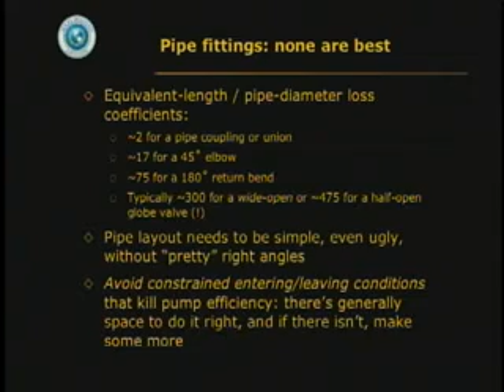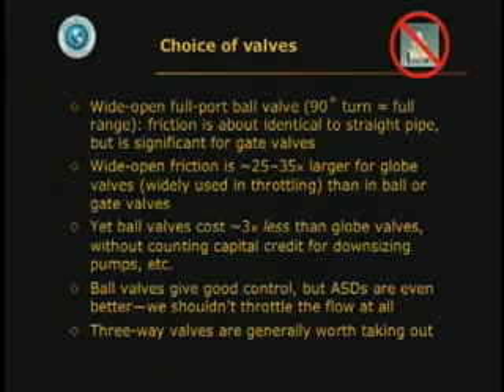A lot of people use globe valves, which should be exterminated. If they're wide open, they have 25 to 35 times the friction of a full port ball valve that's wide open. And by the way, the ball valve is 3 times cheaper, not even counting the downsizing of the pumps to cope with less friction. Ball valves give good control. Globe valves are often put in for control. Don't worry about it. Use electronic adjustable speed drives to get your control instead of throttling the flow. If you got 3-way valves, generally take them out.